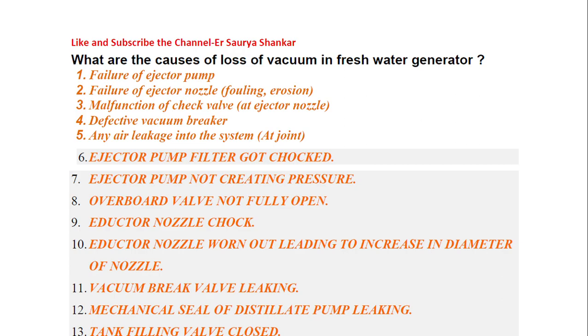What are the causes? There can be many causes. Failure of the ejector pump, failure of ejector nozzle — that can be either fouling or erosion. Because of the turbulence and the pockets that are created, we have erosion or pitting. Malfunction of check valve at the ejector nozzle, defective vacuum breaker, any air leakage into the system at joints, ejector pump filter got choked, ejector pump not creating pressure.